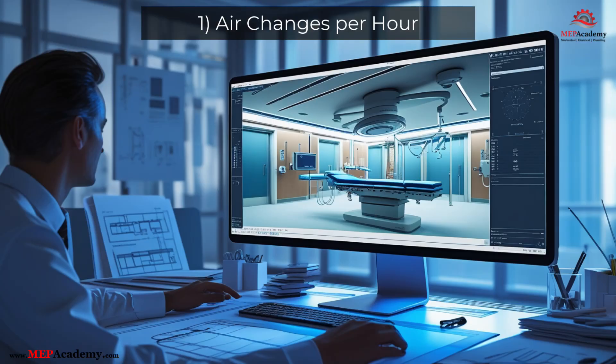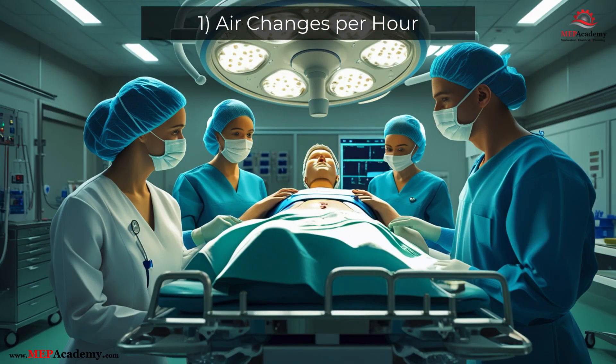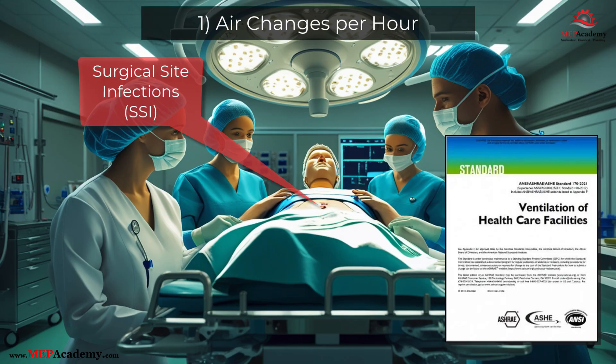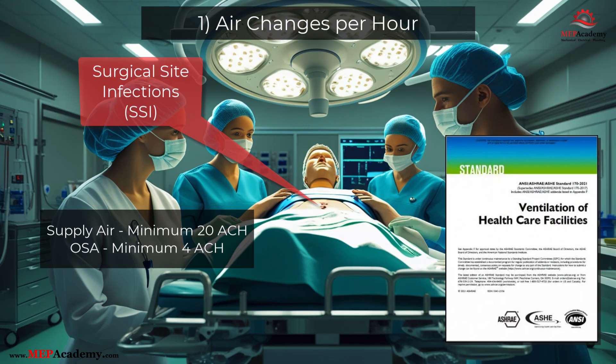Takeaway 1: Air Changes Per Hour. The primary purpose of an operating room HVAC system is to reduce the risk of surgical site infections (SSIs) by controlling airborne contaminants and maintaining a clean, stable environment. According to ASHRAE Standard 170-2021, an operating room must meet the following minimum conditions: air changes per hour shall be a minimum of 20 during occupied surgical conditions, with a minimum of four air changes per hour for outdoor fresh air.